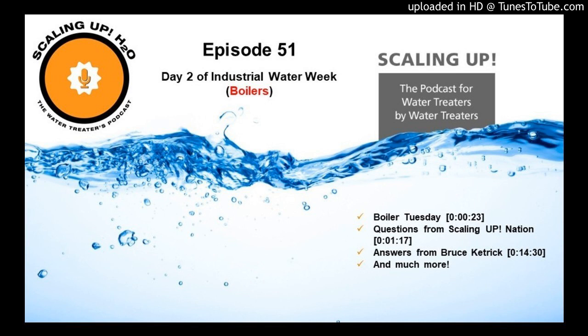And folks, I know you've heard that term before, but maybe it doesn't make complete sense. Why is wet steam such a big deal? Well, it's all about BTUs, British thermal units. Water on its best day can have 180 BTUs in it. Steam, however, on its worst day, will have 1,150 BTUs in it.